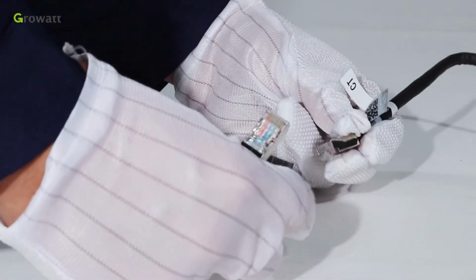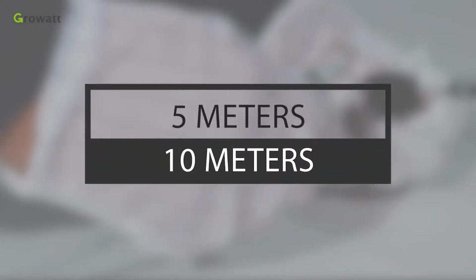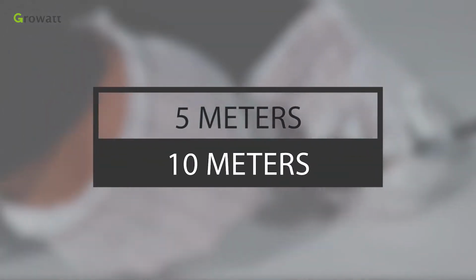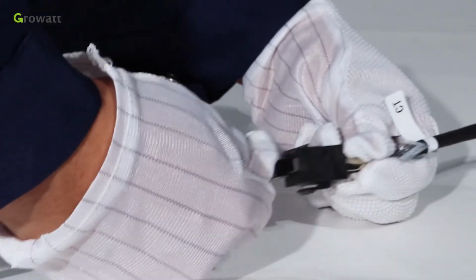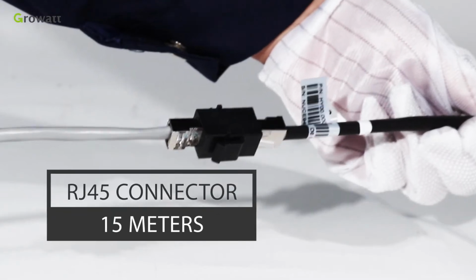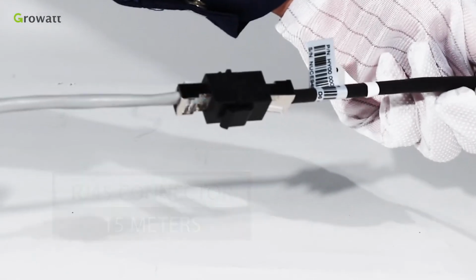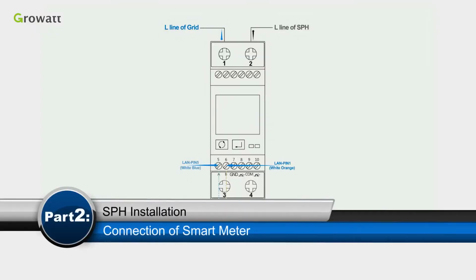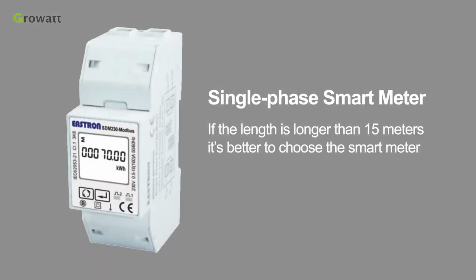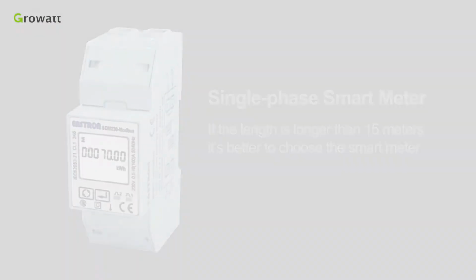Growatt provides two cables, whose length is 5 meters and 10 meters. Growatt also provides RJ45 connector, so the total length can reach 15 meters. If the length is longer than 15 meters, it's better to choose the smart meter.